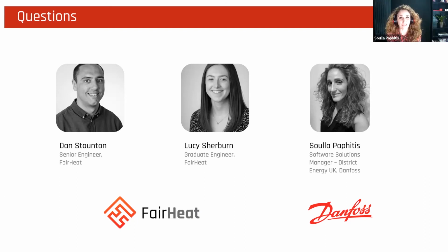They're really great points, Lucy. I would always say that on the kilowatt rating of a plate, there should also be a level where you move from a brazed plate onto a gasketed plate, simply because of the size and the weight of the units themselves. But with a brazed plate, if you're doing around 400 kilowatt, the performance of the plate is better as a brazed plate. And when you look at the maintenance costs and regimes for a 400 kilowatt gasketed plate and what you have to do in the future, it works out that the brazed plate is more cost effective.